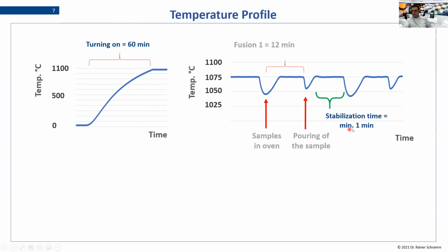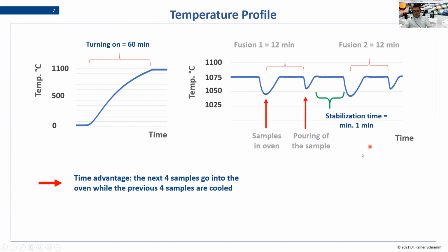It will be 1 minute for routine. And let me say, if you do chlorine or fluorine fusions, then probably it should be something around 3 minutes to give a little bit more time to have exactly the same temperature conditions as before. So then you do your second fusion here. That means we have a time advantage here.